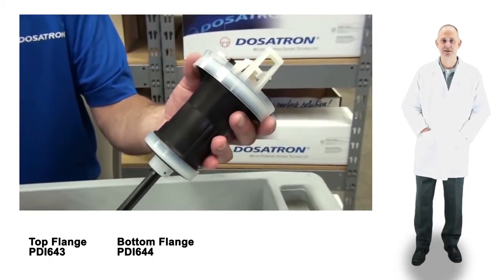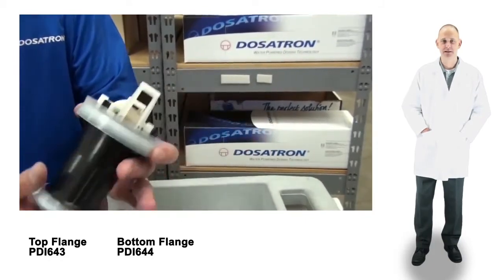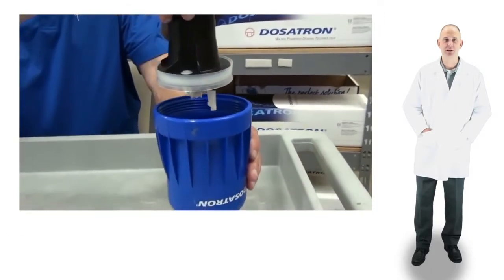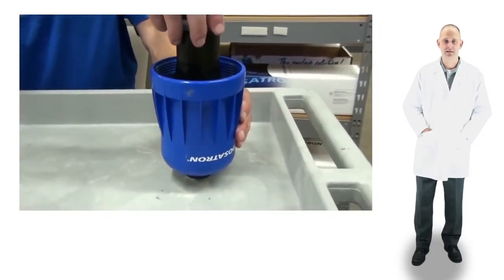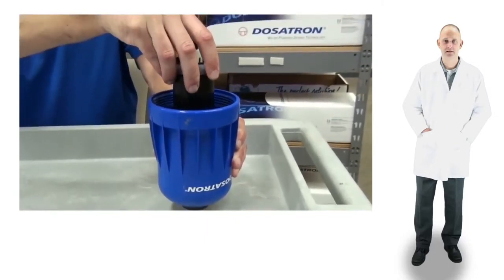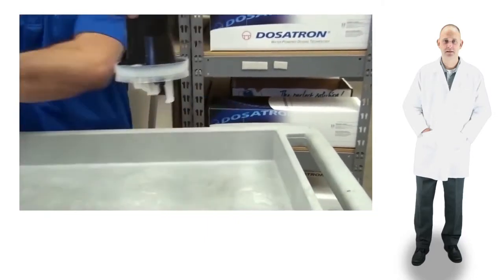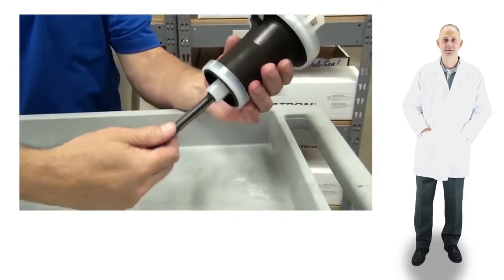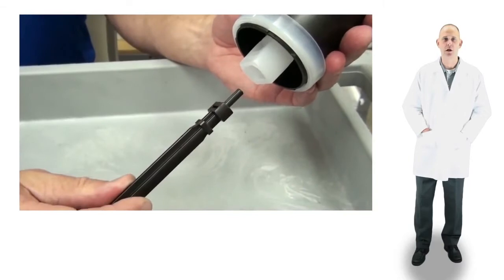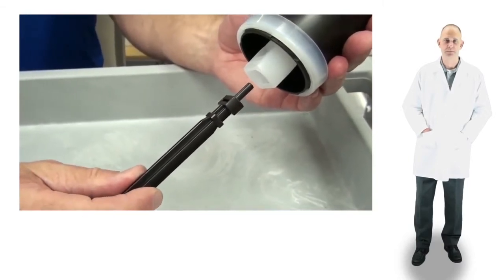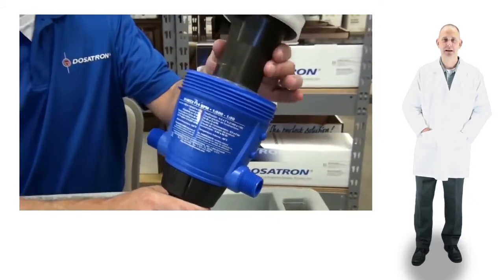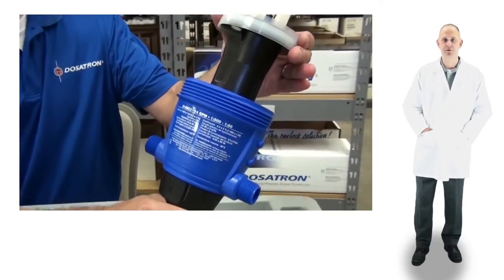Another way to check the flanges is by doing a fit test. To test the upper flange, invert the piston and insert it into the blue bell housing. It should fit snugly. To test the lower flange, remove the plunger by turning it a quarter turn counterclockwise and pulling it straight out. Now, insert the piston into the body. It should be a snug fit. If either is loose, the flanges need to be replaced.